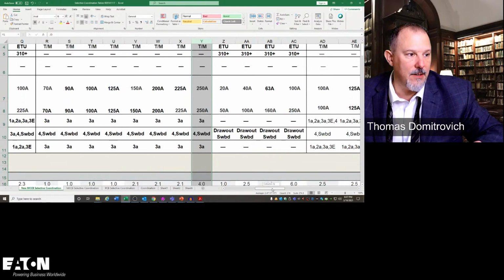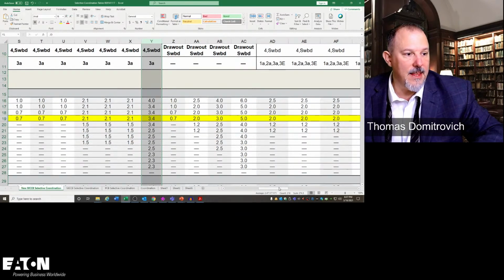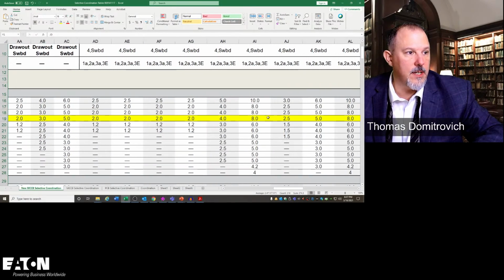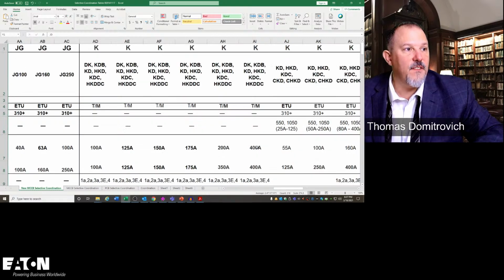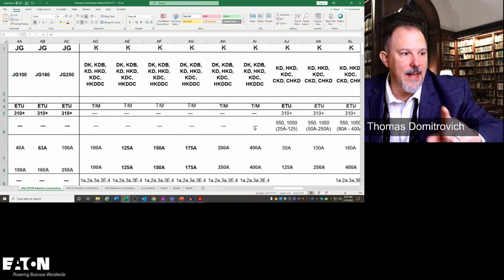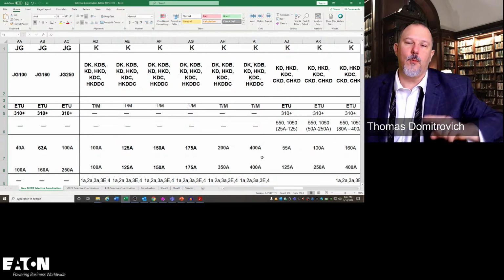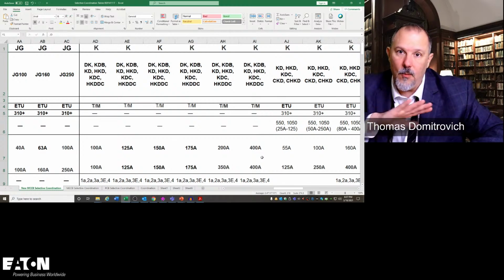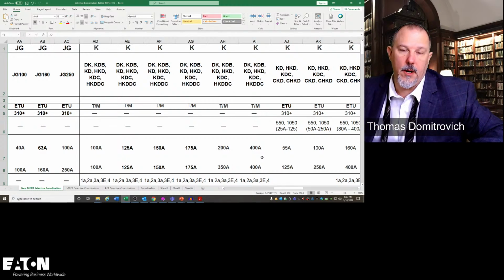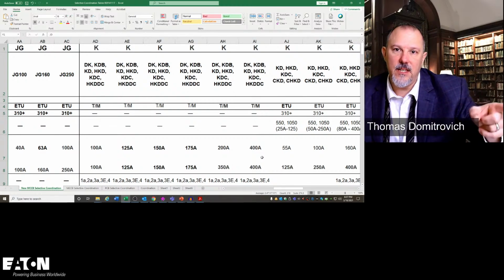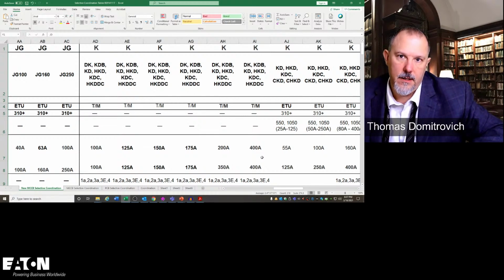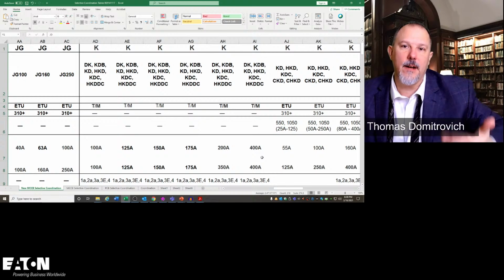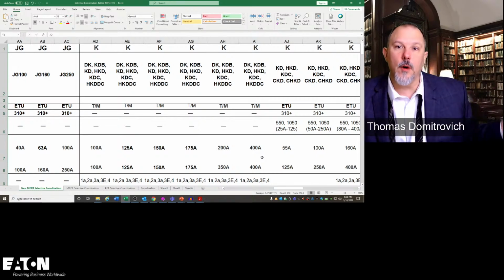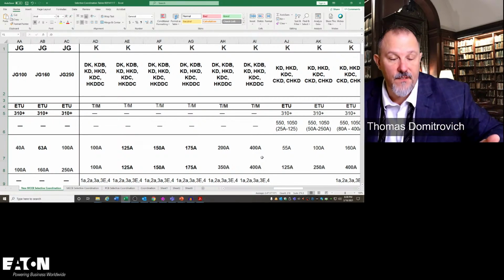Let's go to the 8,000 amps. I'm going to go to 8,000 amps. Where was 8,000 amps? Here's 8,000 amps, 400. If I picked a thermomagnetic 400 amp breaker, what did that tell me? What did I just have to do? If I said, I don't want an electronic trip unit, I'm going to pick a 400 amp breaker. I can't adjust this 400 amp breaker down to 250. What does that mean? I'd have to pick 400 amps worth of conductor. I'd have to put a 400 amp panel board in instead of a 250 amp panel board.